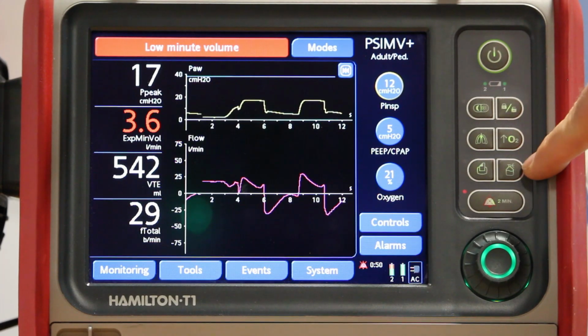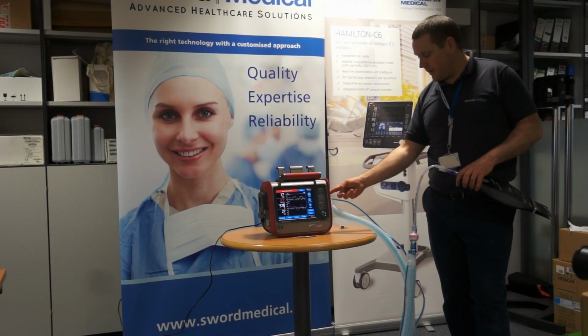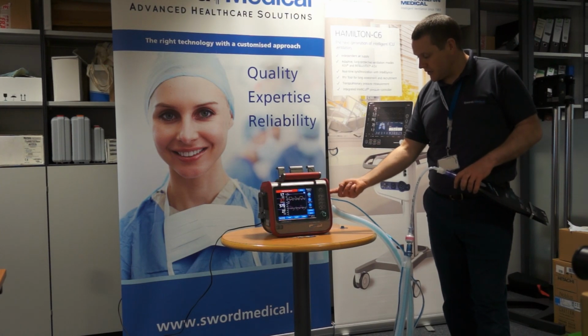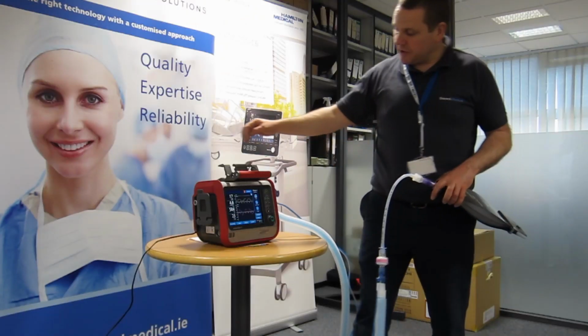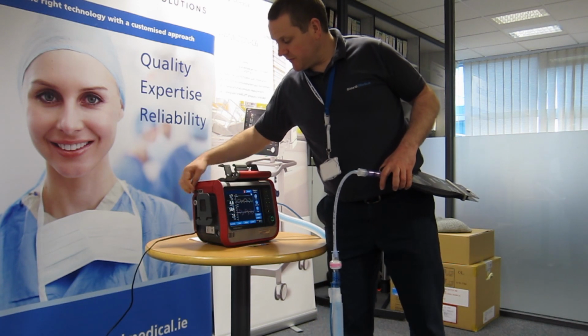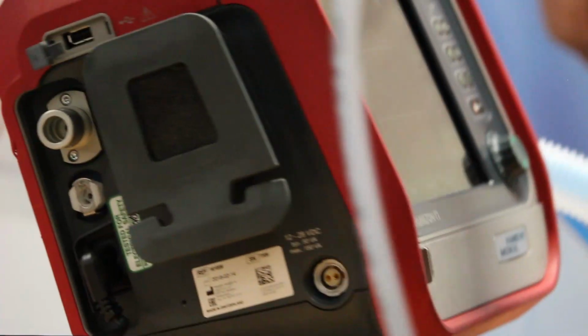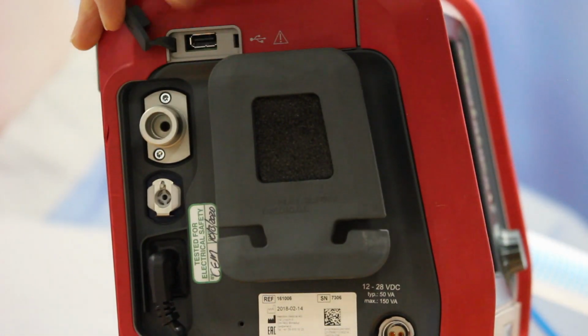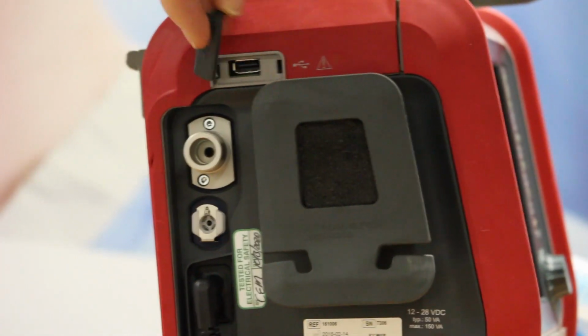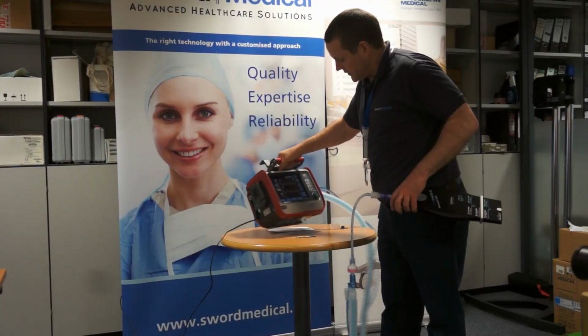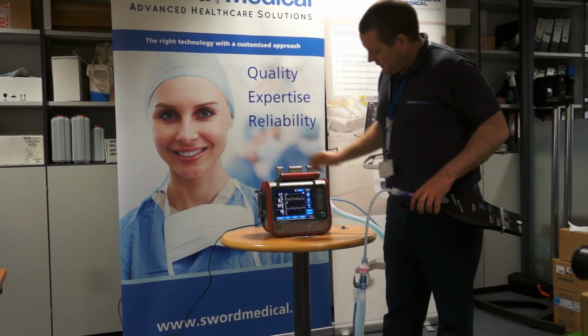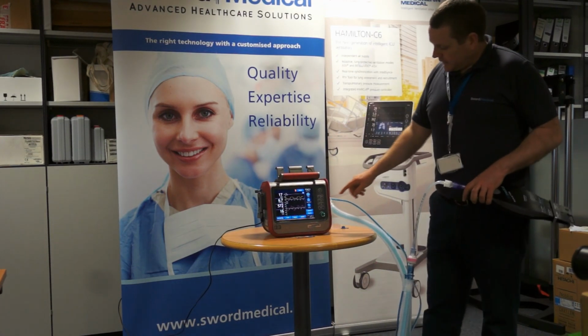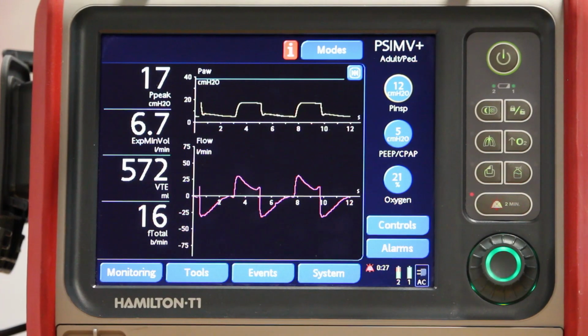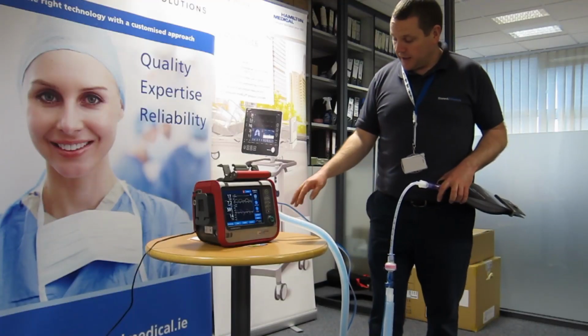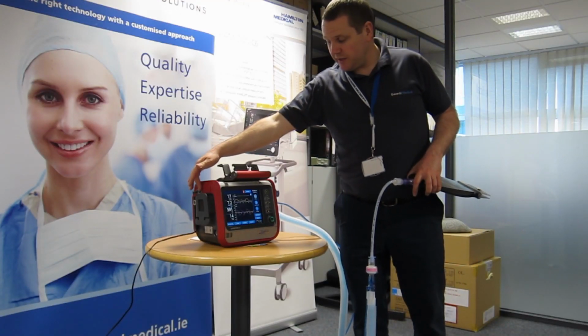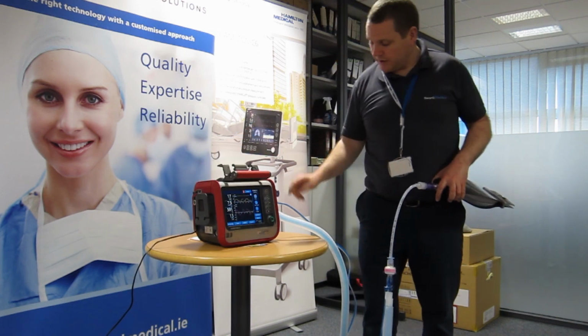My nebulizer button here is for the pneumatic nebulizer, which is on the side of the ventilator here. That turns that one on. If you're using your AeroNeb, Aerogen have a specific lead that has a USB cable attached to it, and that is where the AeroNeb would get its power from, on the USB port on that side of the ventilator. My data transfer button is for the engineers putting on and off software. It's for taking screenshots if you have a USB flash drive plugged into the USB port.